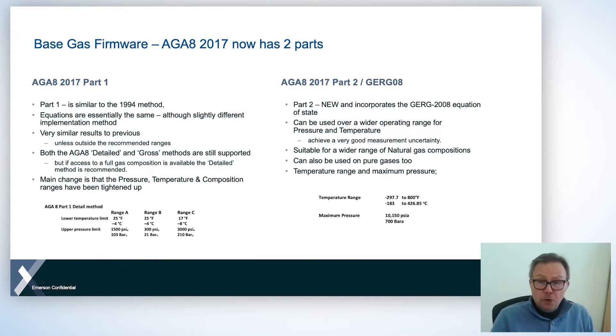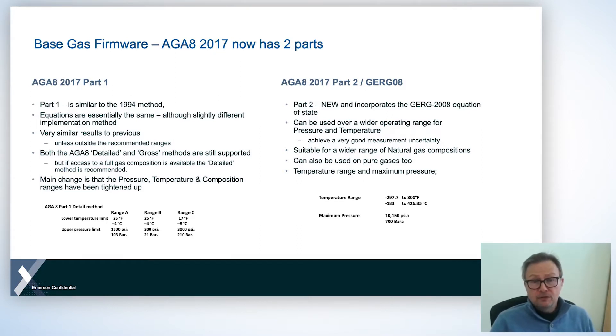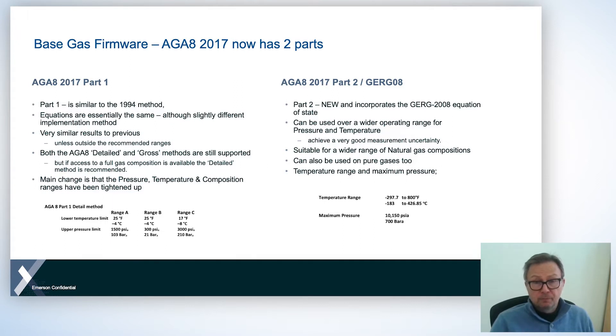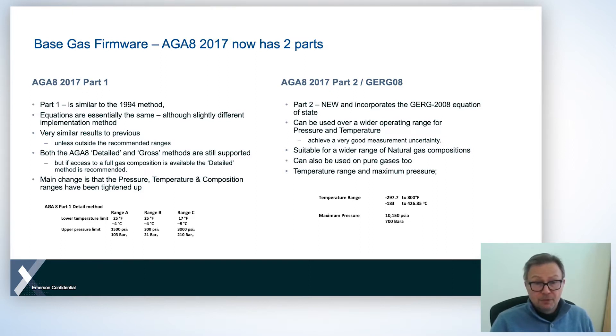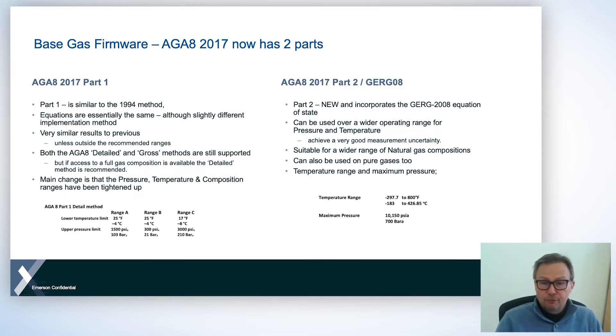If we look at the all-new AGA8 part two, this incorporates the GERG 2008 equation of state. This can be used for a much wider range of pressure and temperature situations as well as a wider range of gas compositions. The temperature range goes from minus 300 to plus 800 degrees Fahrenheit and up to 10,000 PSI.